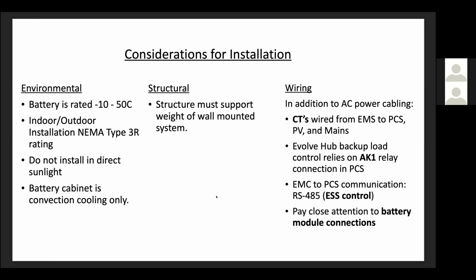Okay, some basic considerations for installation. Some environmental considerations, of course, the temperature rating. The battery is rated from -10 to 50 degrees C. So if you're in a really cold area up in the mountains somewhere, you might want to consider putting it inside the garage. Of course, you don't want to have it in direct sunlight on a south-facing wall because if ambient temperatures, let's say, are 45 degrees, inside that battery cabinet it will exceed that 50 degrees. So you want to make sure that you're on a north-facing wall or it's shaded, if not inside a garage or something like that.